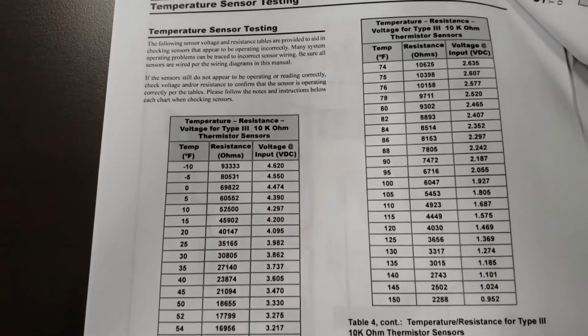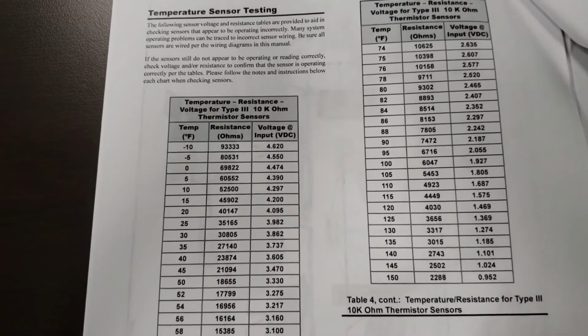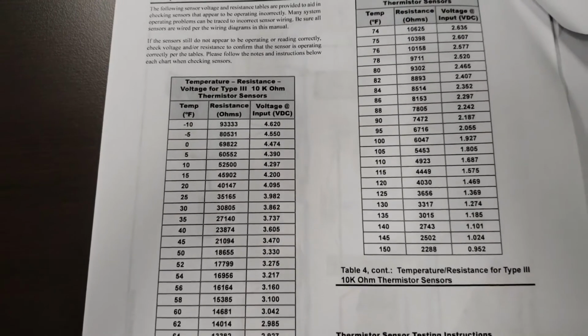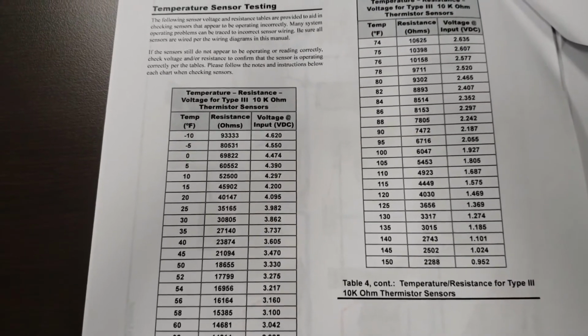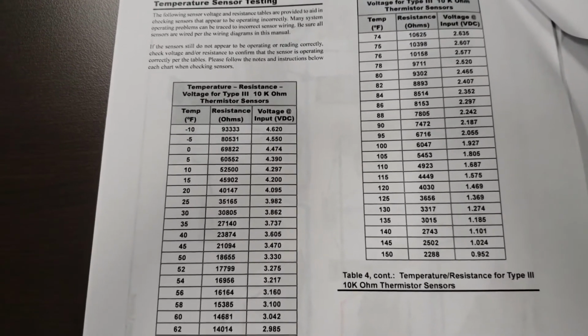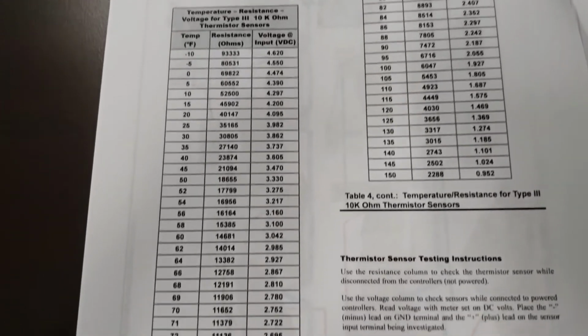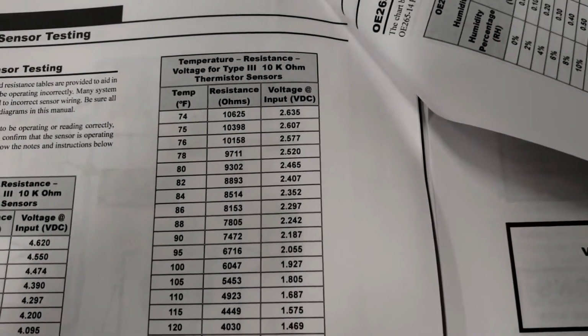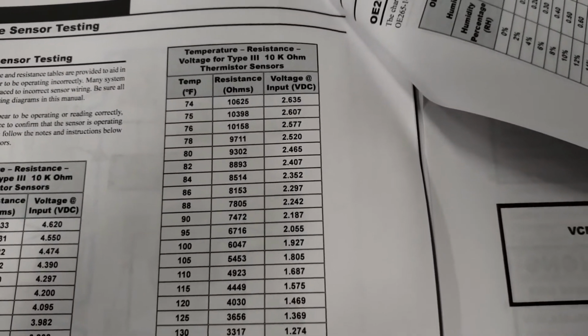Here's your temperature resistance chart. Whenever you're troubleshooting the sensors, 10K on type 3. Can any of y'all tell me what temperature 10K is? 77 degrees. So anytime you're talking about these sensors, it's 10K at 77 degrees.